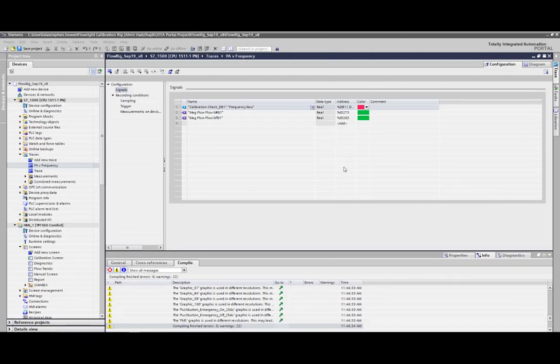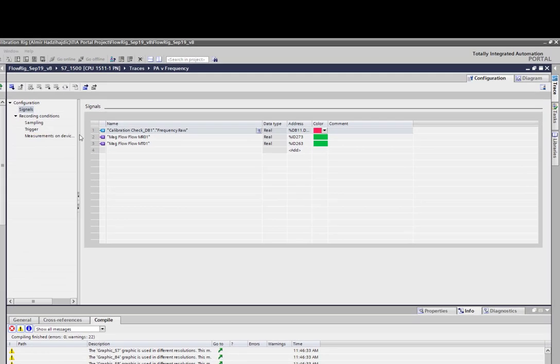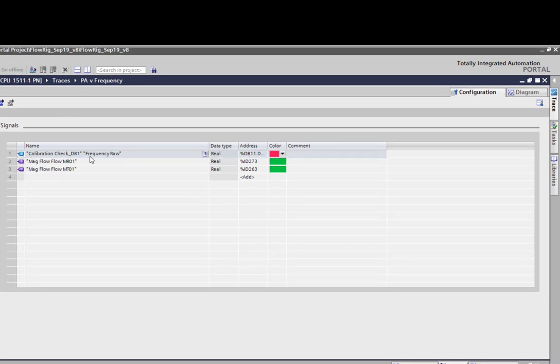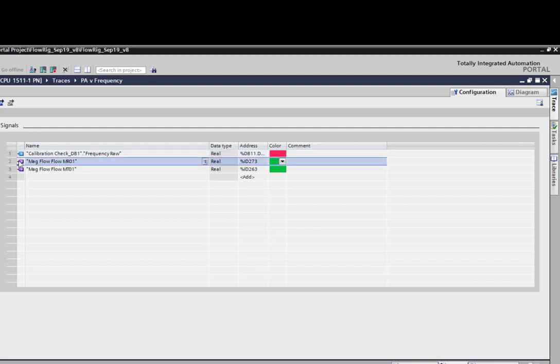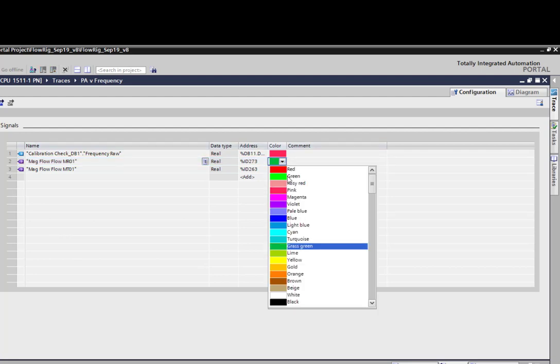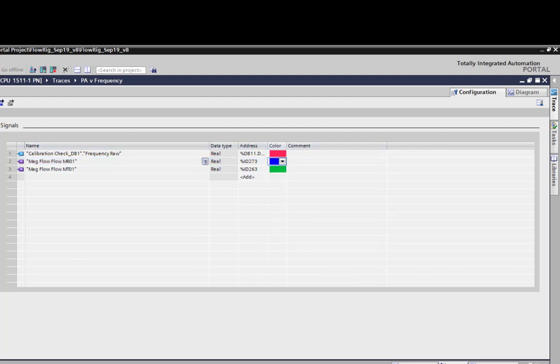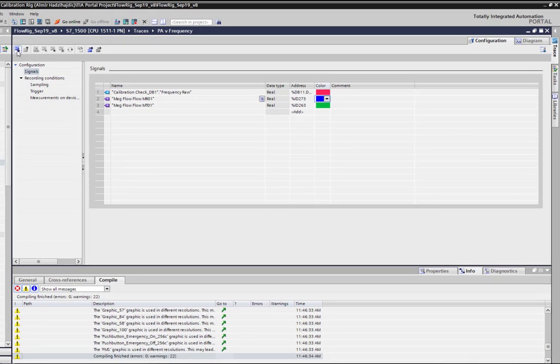You have to add your signals and for this test we've got our calibration frequency raw. So this is the raw value from the high speed counter. The pulses going into this are relatively quick from the flow meter. The flow meter can output up to five kilohertz on the frequency. I've got this going at one pulse every 0.10 of a liter so it's going to be going quite fast. I have then my two PROFIBUS values for my reference meter and meter on the test. Under here you can change the color. Once you're happy with that you're actually downloading that to the PLC.